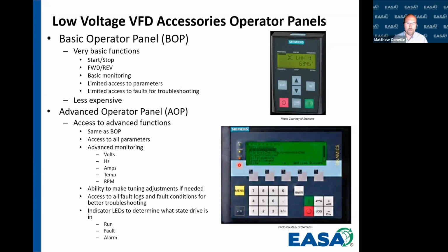The one thing that I found to be most beneficial is you're actually going to have much better access to the fault logs and the alarm logs. A lot of times it'll tell you what the fault condition is, and then what's in the troubleshooting guide of the drive system and the manual. A lot of times they'll put those exact things in there, so you have kind of a tree of decisions you can go through to see what caused the fault to occur. And then you'll also have some indicator lights as well that are going to give you status conditions. And that's going to be your run light, your fault light, and your alarm. And remember, a lot of our alarms are going to be things that we set in the parameter set, some coming from some of the accessories and some coming from just some of the basic parameter sets like ground fault monitoring in the drive system itself.